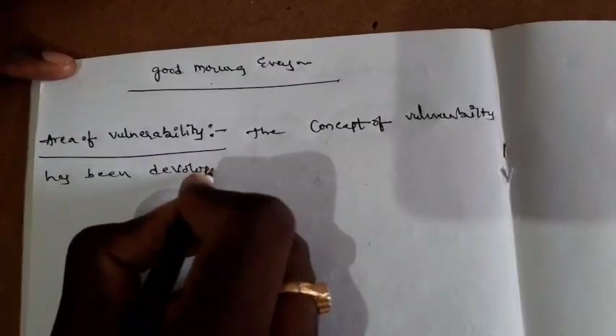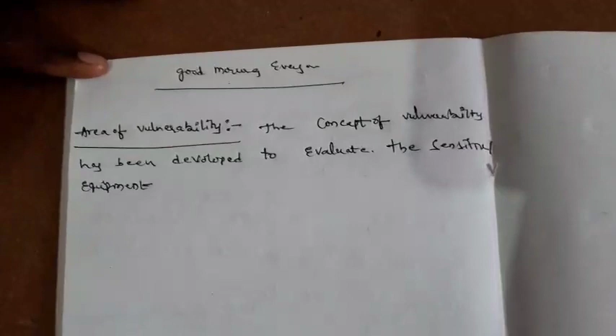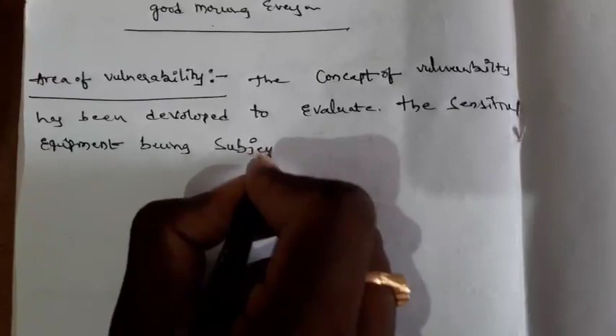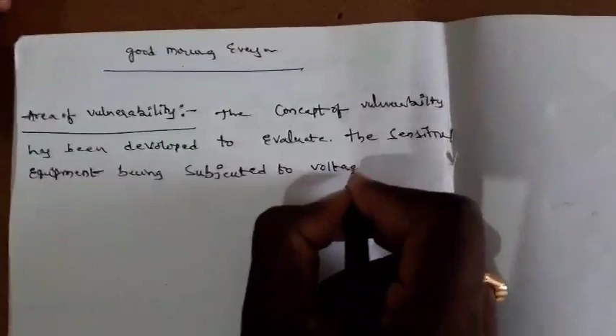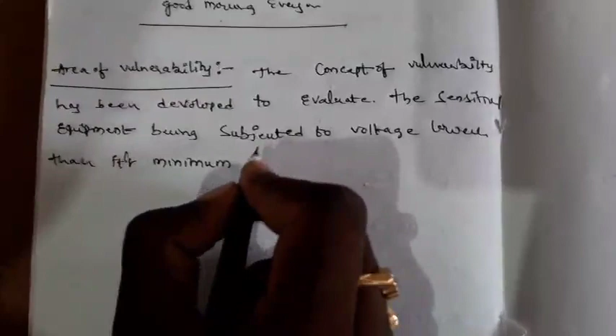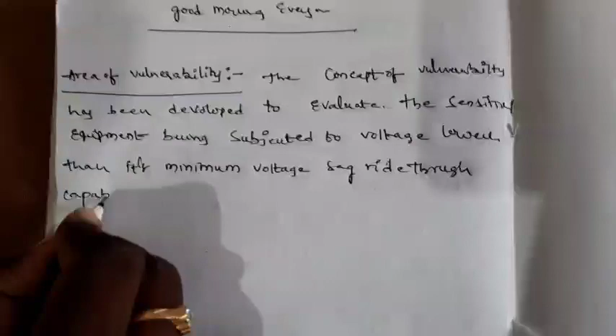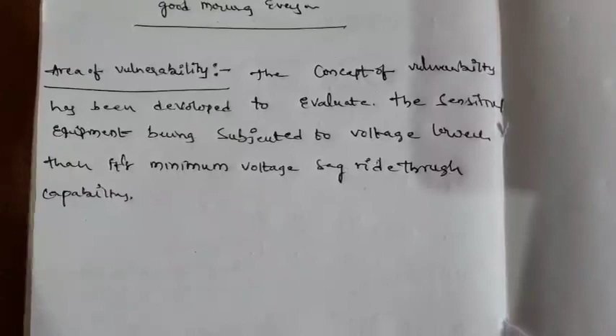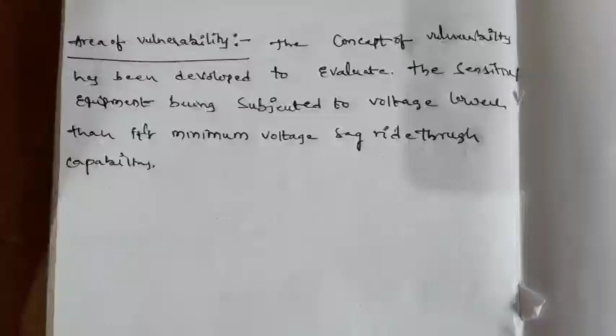So the concept of vulnerability has been developed to evaluate the sensitive equipment that is subjected to minimum voltage, the ride-through capability. Equipment being subjected to voltage lower than its minimum, voltage sag ride-through capability. So that means this can also be said as the piece of equipment that can withstand the minimum voltage.